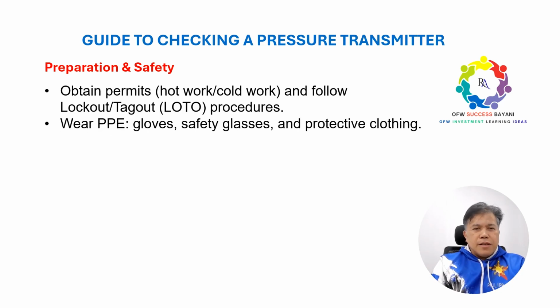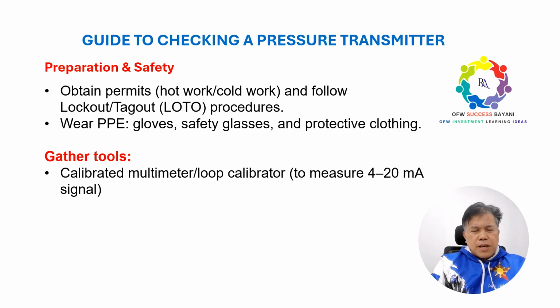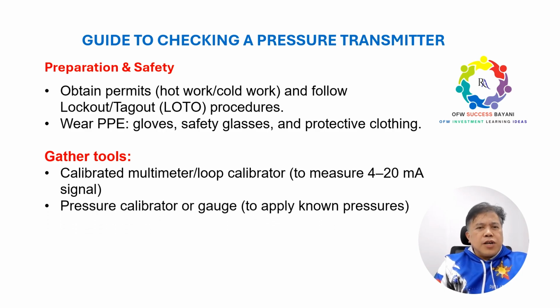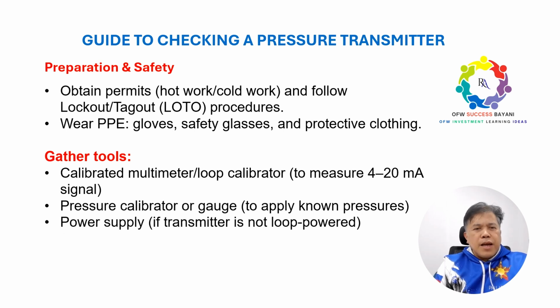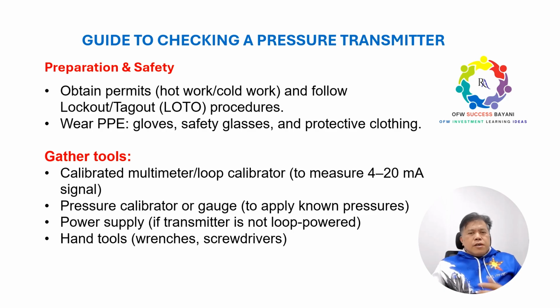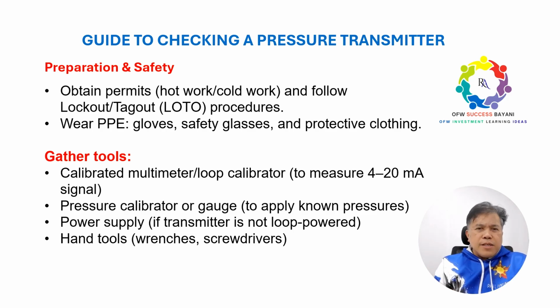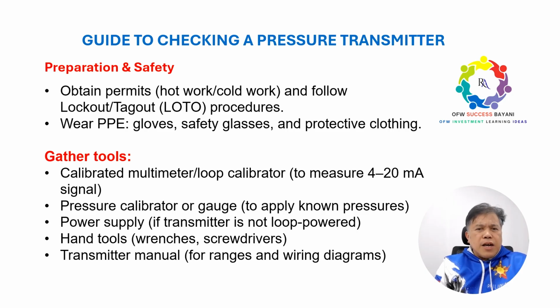So wear complete PPE, meaning PPE that's complete: gloves, safety glasses, and protective clothing like a coverall. And then gather tools, whatever required tools and particular tools that are appropriate for the installation of our transmitter. So a calibrated multimeter, loop calibrator, and of course that is to measure the 4 to 20 milliamp signal. All right. So pressure calibrator or gauge to apply a pressure, and a power supply if the transmitter is not loop powered. So hand tools, any wrench or screwdriver or whatever is required for our activities. Now, transmitter manual, range and wiring diagram.